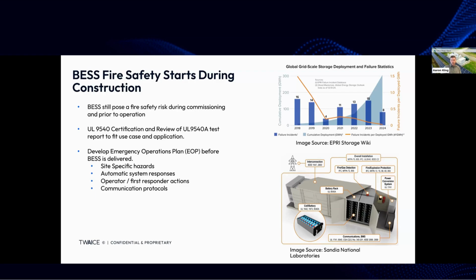There is a risk present even before the commissioning and operation of batteries. There were two high-profile battery fire events in New York State in 2023, both of which occurred during commissioning, before the systems were placed in service. For this reason, we now recommend that projects create an emergency operation plan, also called an emergency response plan, before the BESS are delivered to the site.